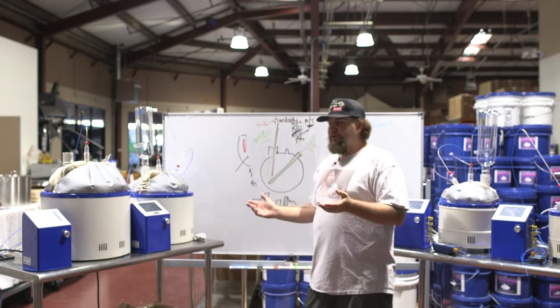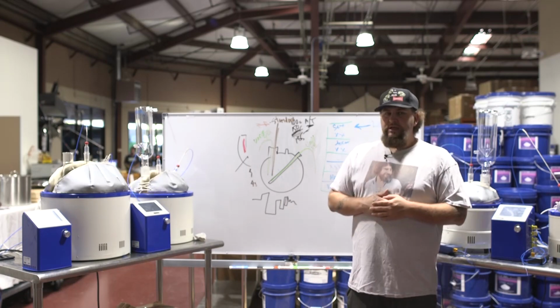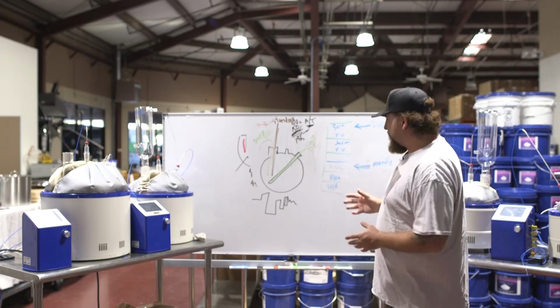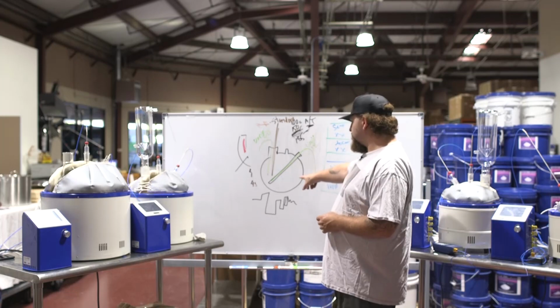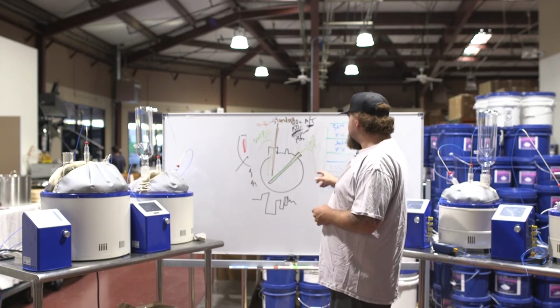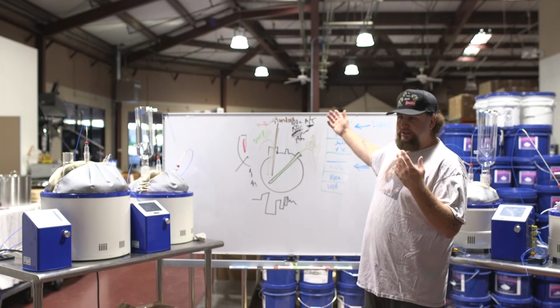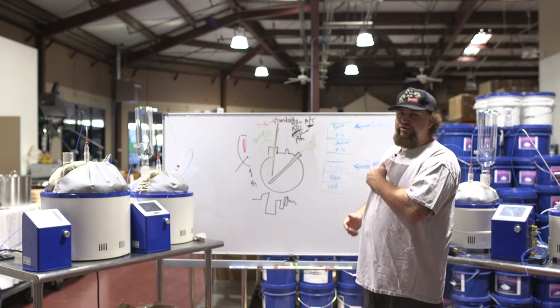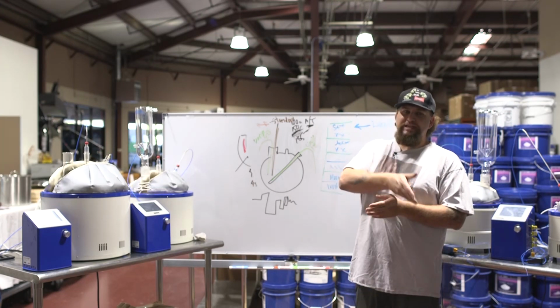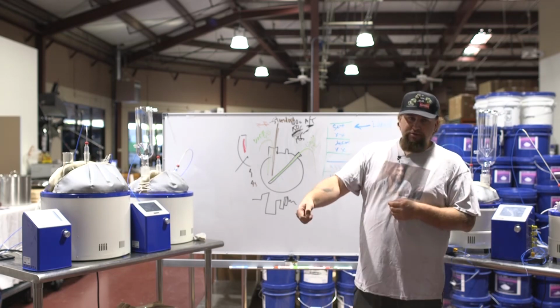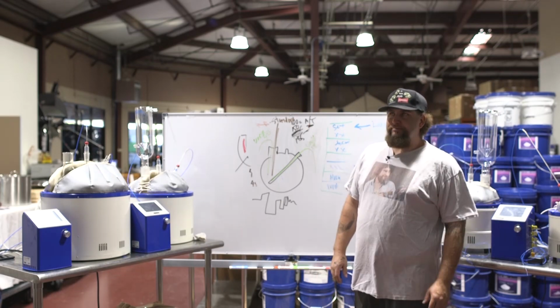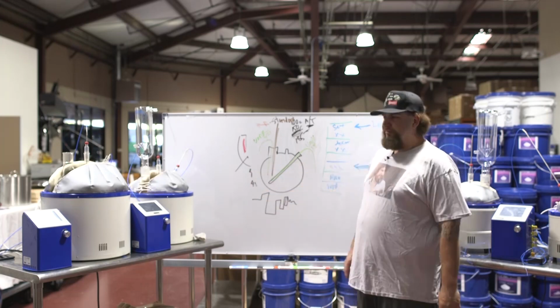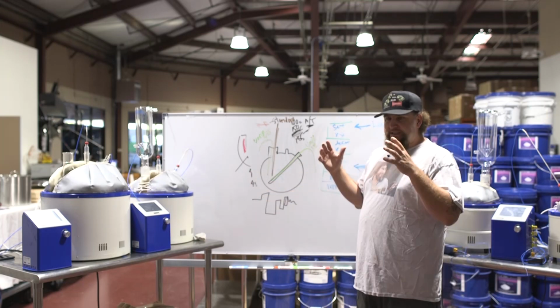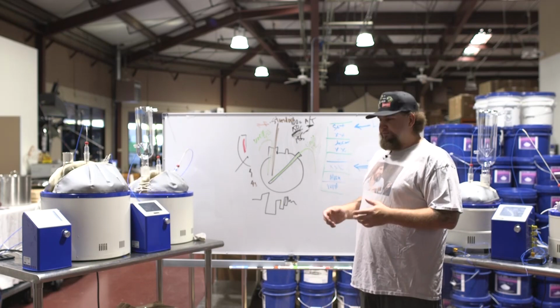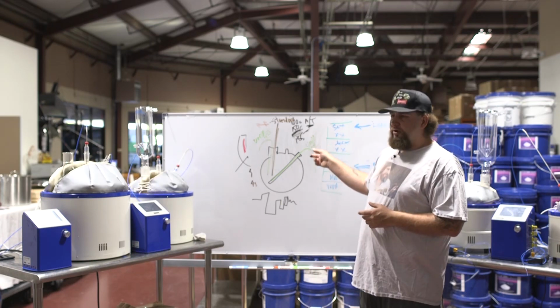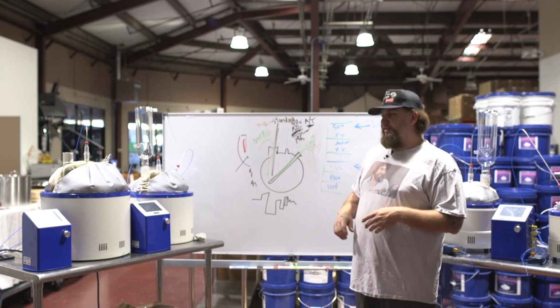So here's some of the cool features, and this is the actual methodology of tuning. Now, if you do it the other way around, let's say their mantle bowl is attached to here, right? Essentially, all of this is roughly the same hookup. What you're doing is you get it to temperature. So I would put my thermometer in there after it's on vacuum, and I'd bring it up to 175 and just see what happens to the system, maybe 160. And then once the system itself stabilizes on its own with an auto-tune, I'll put the thermometer in there, and then I set my deviations.